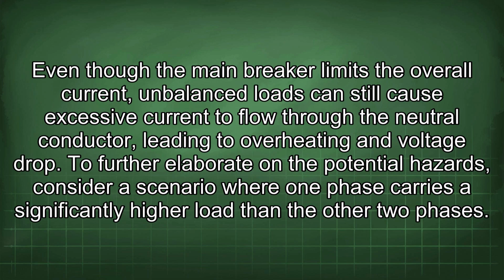Even though the main breaker limits the overall current, unbalanced loads can still cause excessive current to flow through the neutral conductor, leading to overheating and voltage drop. To further elaborate on the potential hazards, consider a scenario where one phase carries a significantly higher load than the other two phases.